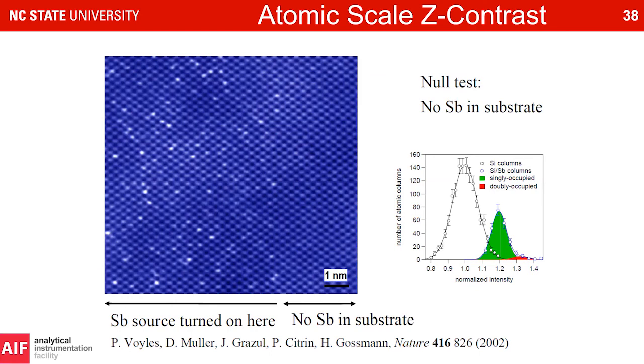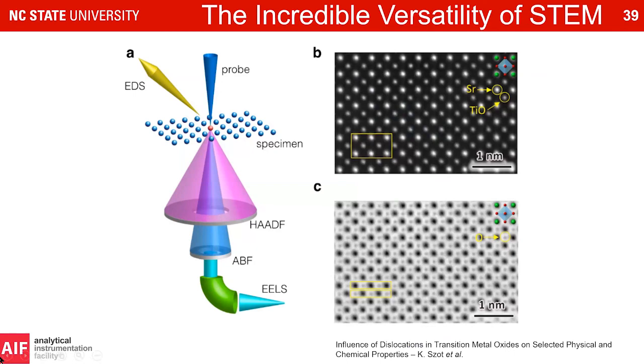One of the reasons STEM is so powerful is that you can do a lot simultaneously. We illuminate our sample with a small probe, scatter electrons to different angles, collect the high-angle signal, collect signal at different angles, collect the EELS energy-loss signal, and collect the EDS or x-ray signal — all at the same time. We can get four, five, or six datasets from the same sample in the same microscope session. STEM is dominating right now because of that incredible versatility and improvements in optics and resolution.